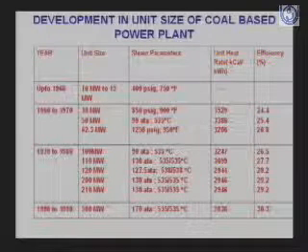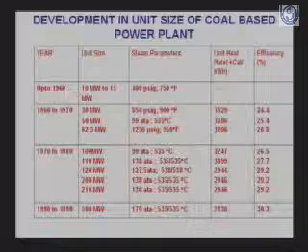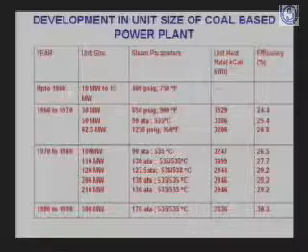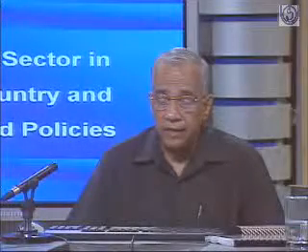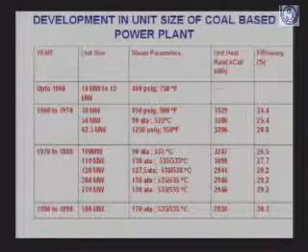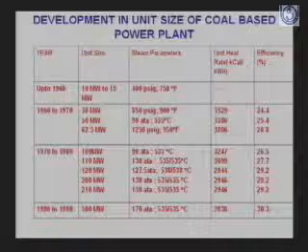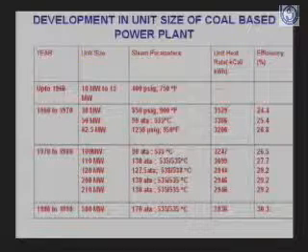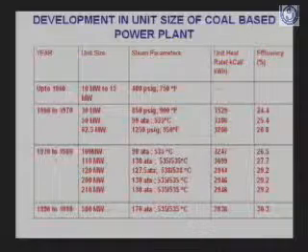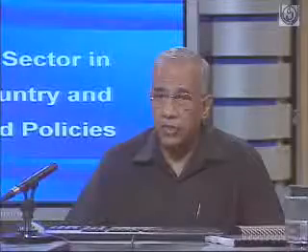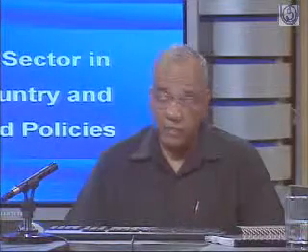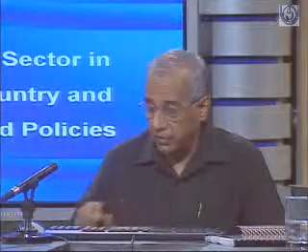In the beginning I told you that at the time of independence and in the year 1980, even 55 year old machines were existing in the country, and therefore if one keeps them running with proper maintenance, one can definitely increase the life of the machine. So I was explaining that the temperatures have something to do with the metallurgy. The pressure also has something to do with the metallurgy, because pressure and temperature combined can become very stressful for a pipe which is carrying the hot steam.